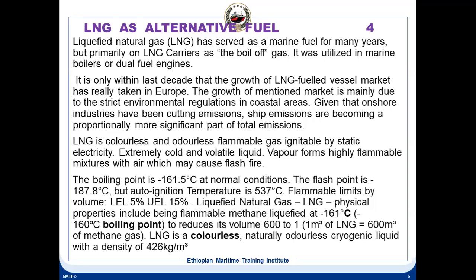And one more is the flammable limits. You see the flammable limits are 5% and 15%. 5% is called the LEL, that is the lower explosion limit. The lower explosion limit is 5%, and the upper explosion limit is 15%. So within these two brackets, between 5 and 15%, it is flammable. If it is less than 5%, it is not flammable because the concentration of LNG, or methane, we can say, because methane is the main constituent of the LNG. Methane is the main one.